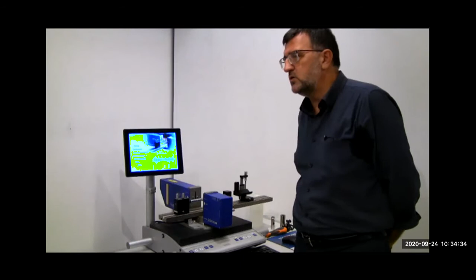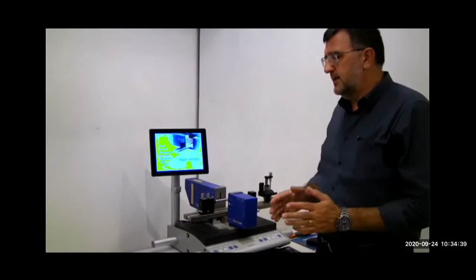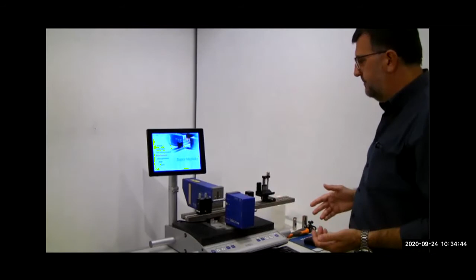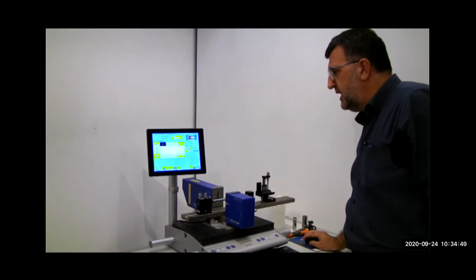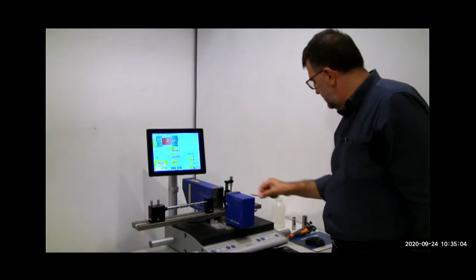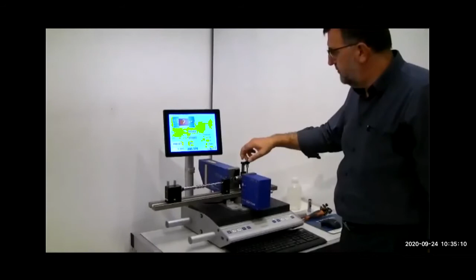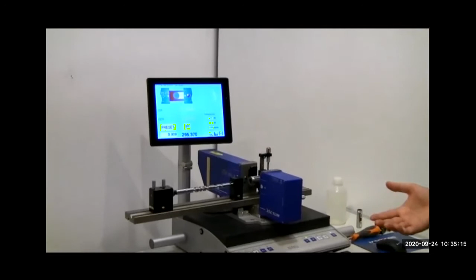There are systems that are calibrated only in the factory, because we make our calibration with a set of masters that start from the minimum measurement diameter to the biggest measurement diameter, so the system is perfectly linearized for all the measurements. Like you can see, I can put a 4 millimeter object, or wait a moment, I also have to put down the V block, and it does not need any type of calibration.